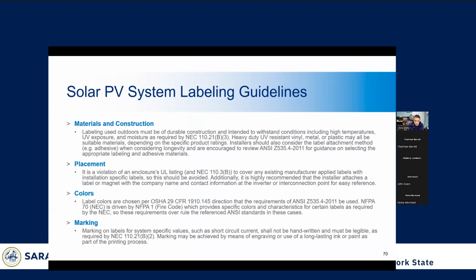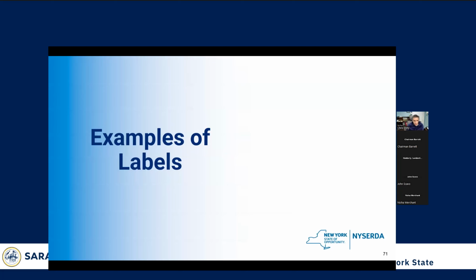And so the main thing to keep in mind is the most dangerous label is a wrong label. It's not a missing label, right? If there's no label, that's bad, obviously. But if you have the wrong label, it can provide whoever's working on the system with a sense of security that they know what they're getting into, and they may act based on that. And if it's wrong, then they can potentially get shocked, or worse, they could potentially die. So the worst thing is a wrong label, and then after that, it's a missing label. So now we're going to go through some examples of labels that are required for solar projects. Again, all PV signage is yellow, orange, or red in color, so it's easily identifiable for electricians and code officials to find.